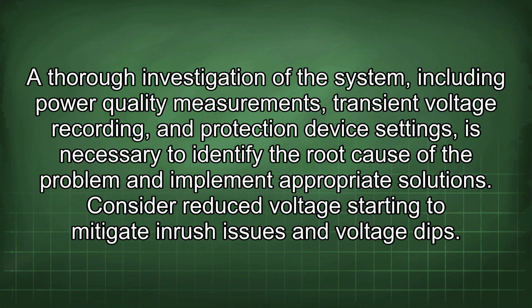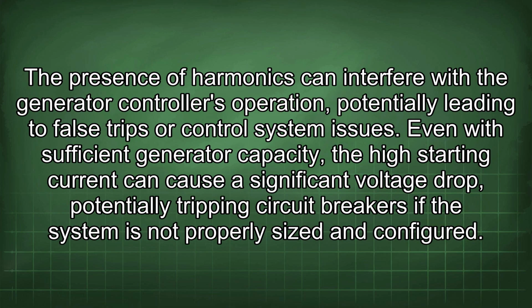Consider reduced voltage starting to mitigate inrush issues and voltage dips. The presence of harmonics can interfere with the generator controller's operation, potentially leading to false trips or control system issues. Even with sufficient generator capacity, the high starting current can cause a significant voltage drop, potentially tripping circuit breakers if the system is not properly sized and configured.